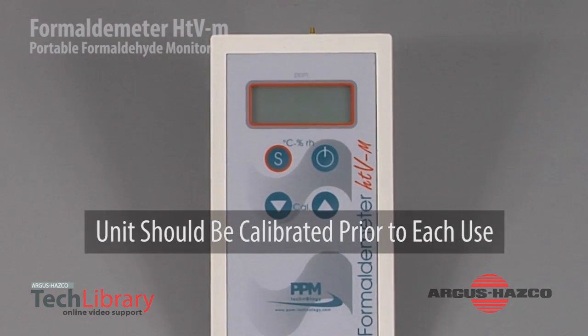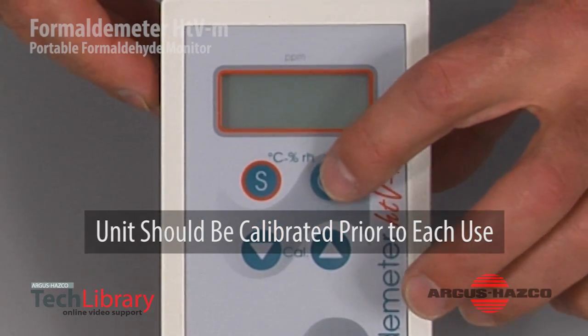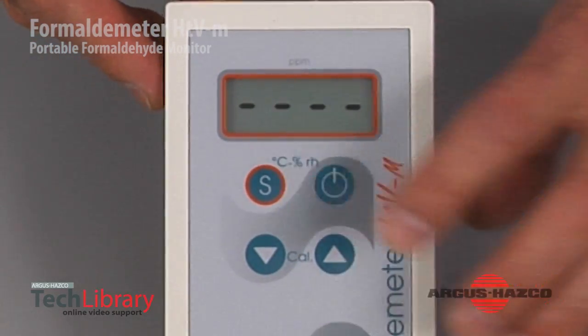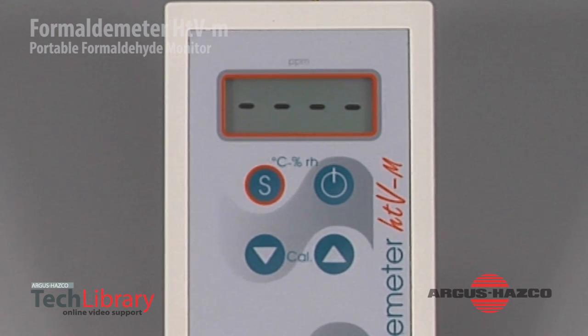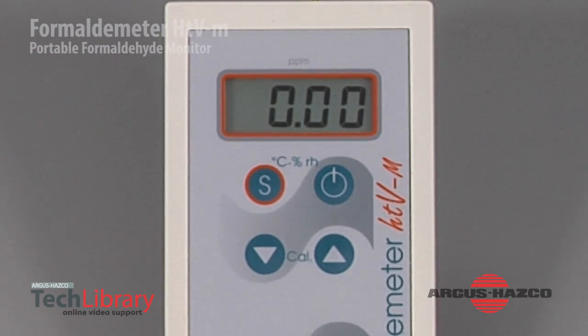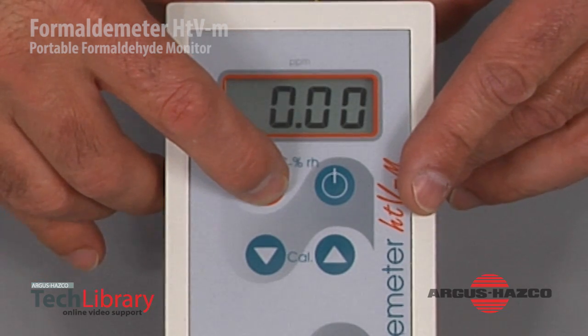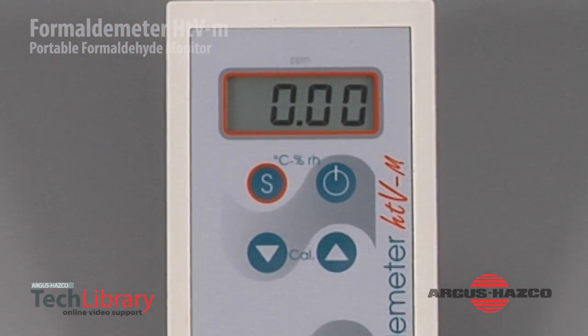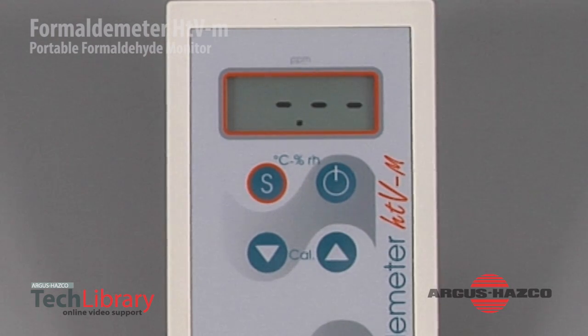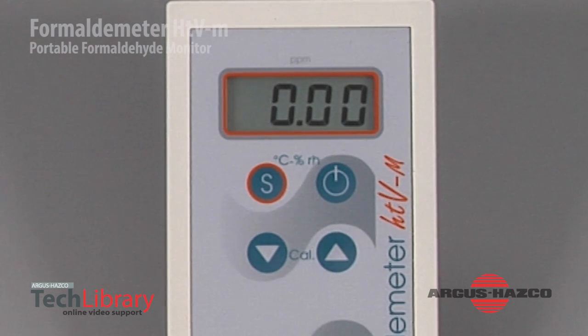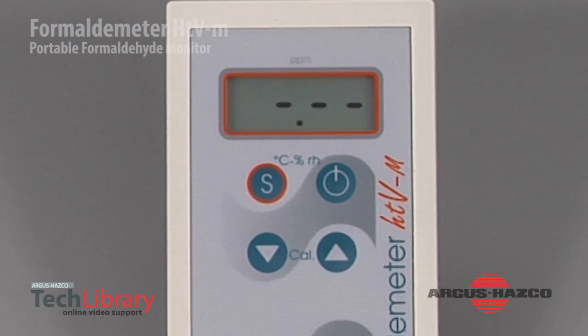To take a sample with the handheld device, we first turn the instrument on. It'll be a series of dashes. It will stabilize to let you know it's ready. Once you see the zeros, you can take a sample by pushing the S key. It indicates run, pulls its sample through. There's a series of dashes and zeros that will flash for 10 seconds. And then it'll start to analyze, which is about 60 seconds to complete.